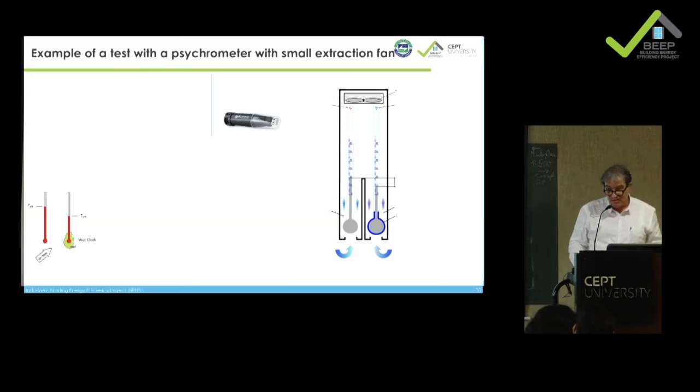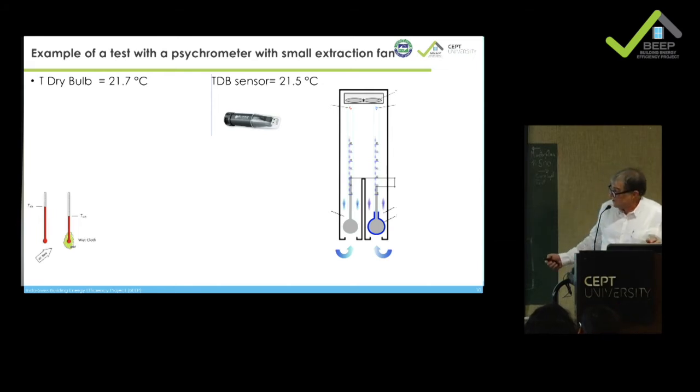At home actually in Switzerland, so it does not relate to the Indian climate, but it's still the same. Now if you look, we had a classical thermometer and a so-called modern electronic sensor, and the two were giving approximately the same dry bulb temperature. Then what we did was, this is the measurement that corresponds here, and then we have the dry bulb, and we try to measure the wet bulb. How did we do it?